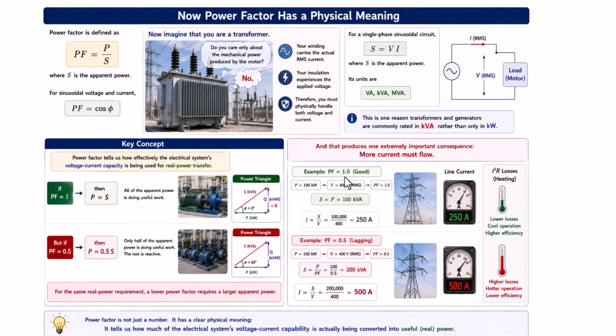Now, the power factor has a physical meaning. Power factor is defined by P divided by S. Here S is the apparent power. For sinusoidal voltage and current, power factor is equal to cos phi. Let's imagine that you are a transformer. Do you care about only the mechanical power produced by the motor? No. Your winding carries the actual RMS current. Your insulation experiences the applied voltage. Therefore, you must physically handle both current and voltage.